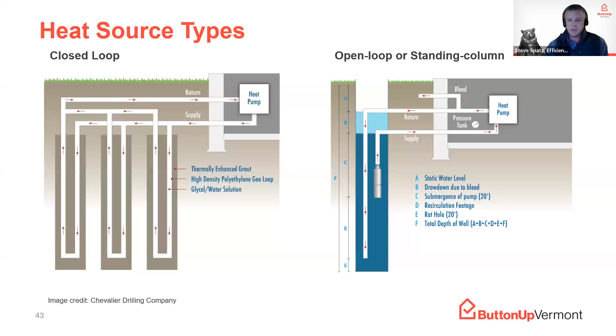Let's cover the variations in performance between the two different types. With an open loop system, you can utilize existing wells or water wells. Water quality has a huge factor in doing open loop systems, the type of water that you're actually pulling through the system. So if you have hard water or minerals in your water, that can be a problem for an open loop system. But the big thing that you're investing in here that's different than the other types is the drilling and the ground source that you're going to be using and utilizing for the heat pump system. So this is where the expense of the system can be impactful.